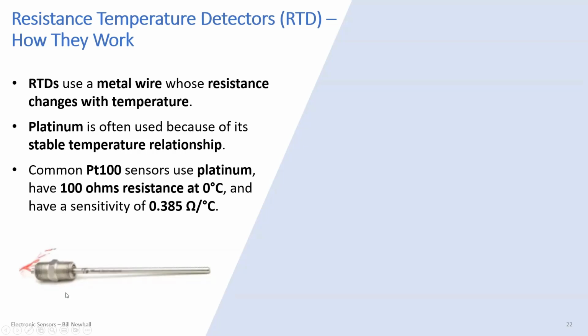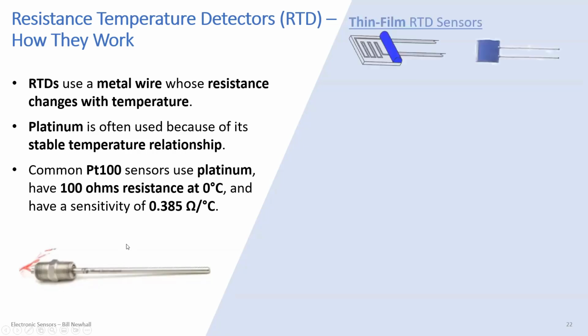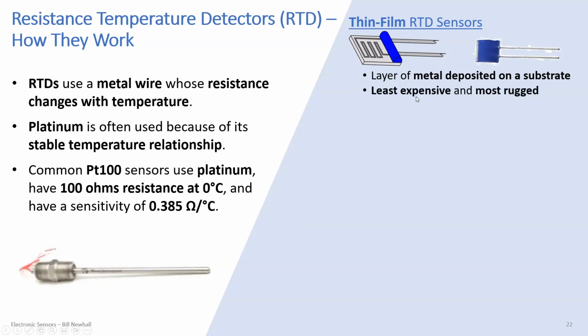And there are different ways to build these up. So here's an example at the lower left here. But there are also other types, like this thin film sensor. So this thin film sensor has a substrate, so that gray block in this cartoon is a substrate. On the right, these are the leads in the cartoon. Here's a real device on the right here. This is a thin film RTD. And then metal is deposited on that substrate, and you see this kind of racetrack here, so that you get a longer wire for a bigger resistance change. And these are the least expensive and generally the most rugged, these types of RTD sensors. But there's a trade for everything. And these are considered to be the least stable RTD, okay? The least stable of these kinds of detectors.